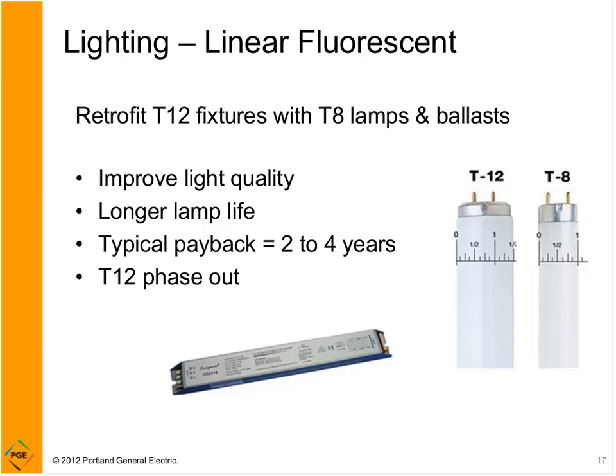So there's a lot of benefits to upgrading from T12 to T8. Typically, you don't have to replace the entire fixture. You can retrofit the fixtures, just a lamp ballast replacement, often lamp holders too. So improving the light quality. One of the metrics of light quality is color rendering index, and this is basically the ability of artificial light to accurately display colors. So the color rendering index of a T8 is going to be much better than T12 typically. You're going to see much longer lamp life with a T8 lighting system over a T12. Some of the newer high performance T8 lamps are lasting in the 24 to up to 50,000 hours. Standard T12 is going to be in the 20,000 hour range. So a lot less frequent replacement of the fluorescent tubes.